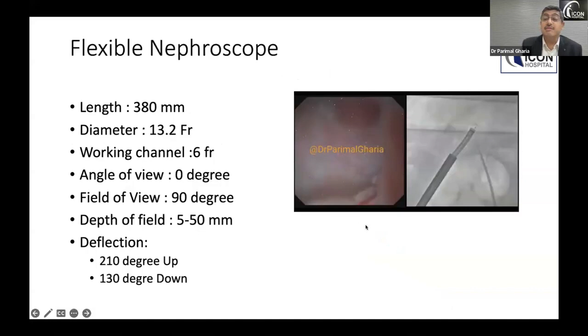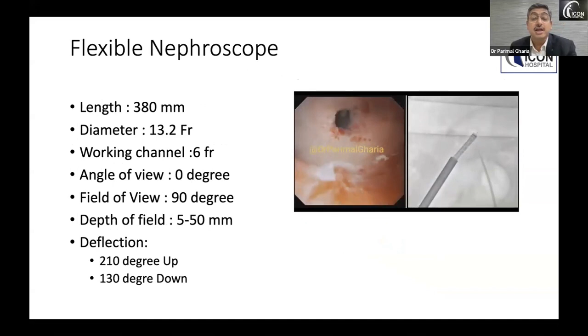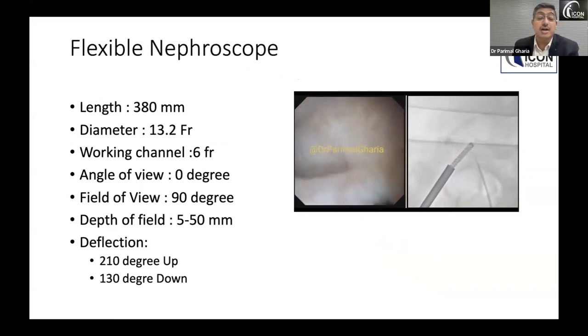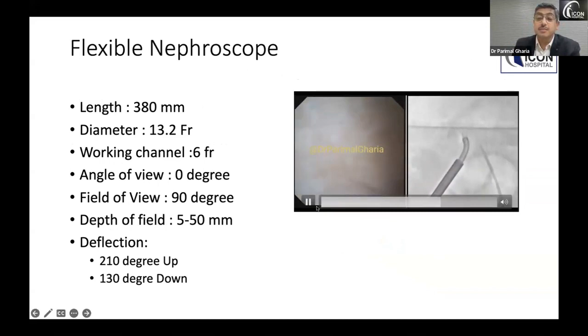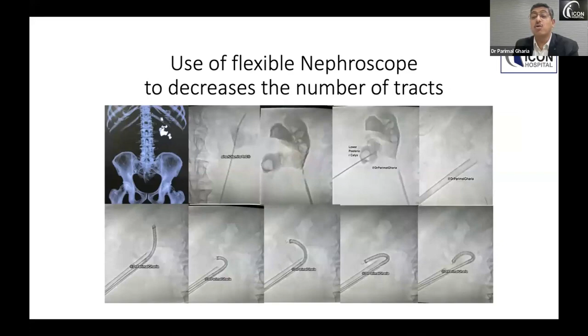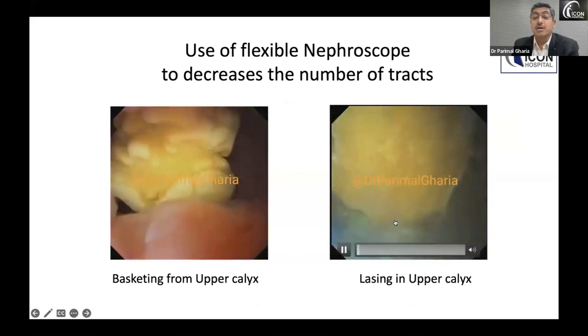Then comes the flexible nephroscope. The newer flexible nephroscope has a 13.2 French diameter and it is chip on tip technology. The angle of view is 0 and it has a deflection on one side of 210 degrees, but on the other side only 130 degrees. You can see that a staghorn can be cleared by this flexible nephroscope by a single puncture because it can be molded into all the calyces. You can see the flexible nephroscope used in the upper calyces from the lower calyces.